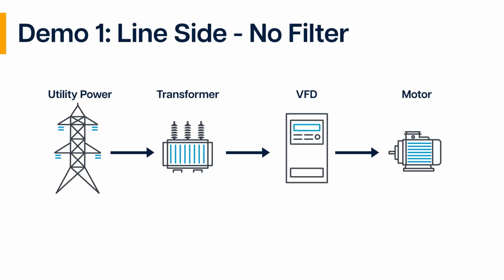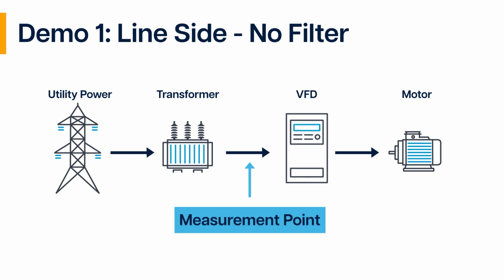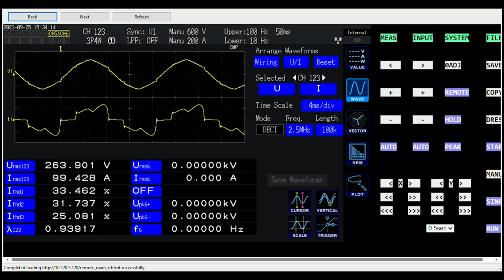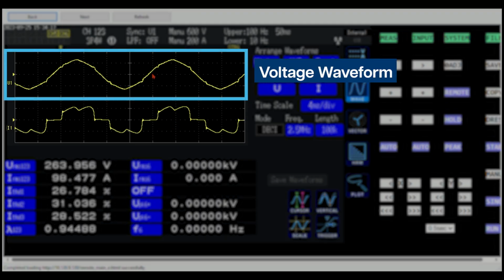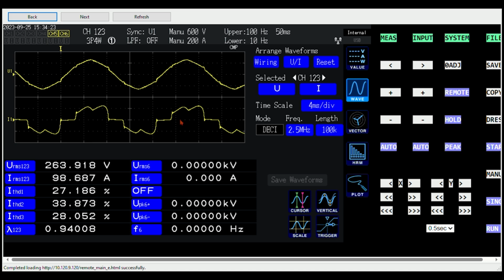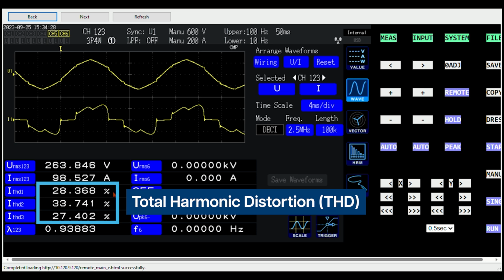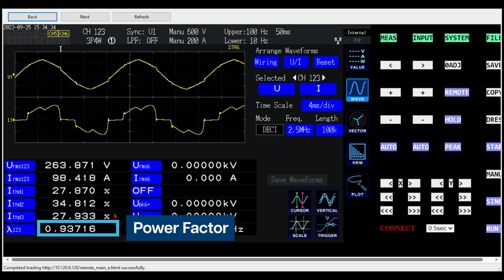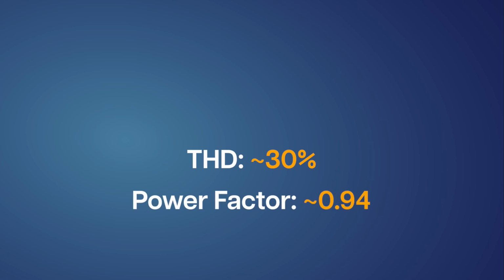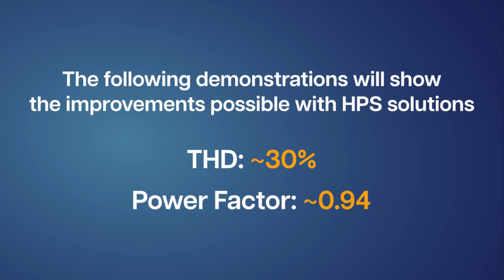The kickoff of our demonstration includes baseline measurements at the VFD input without any harmonic mitigation solution, using a 100 horsepower motor drive set. This particular VFD includes a DC link choke, setting the stage for our demonstration. Initial observations show an average harmonic distortion around 30% and a power factor of approximately 0.94. This baseline serves as a reference point to illustrate the significant improvements achievable with our solutions.